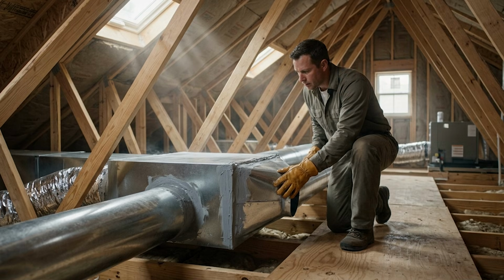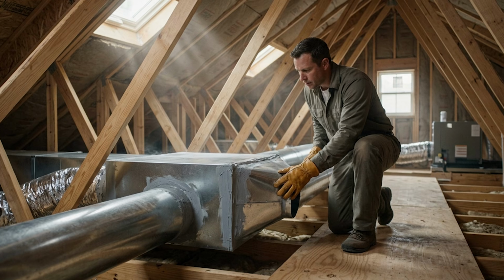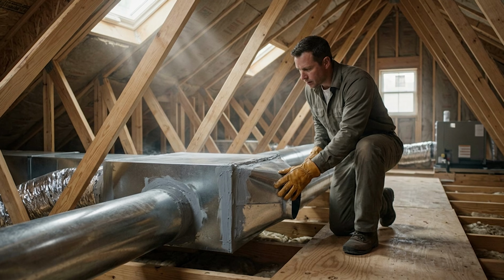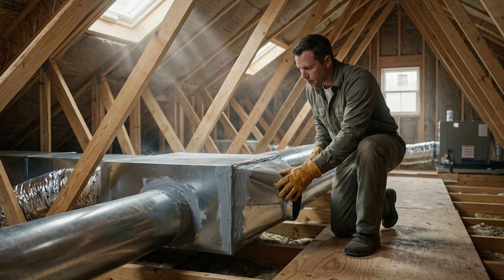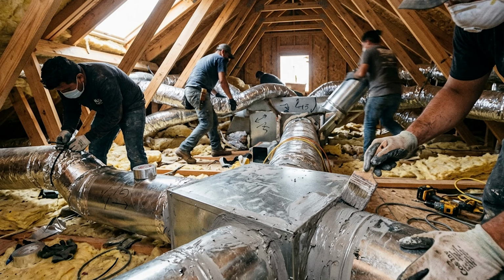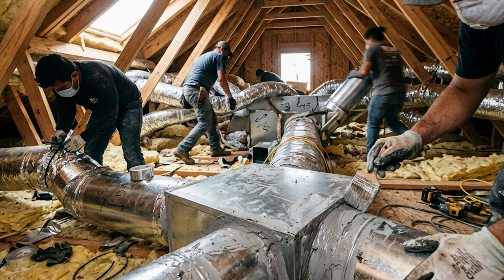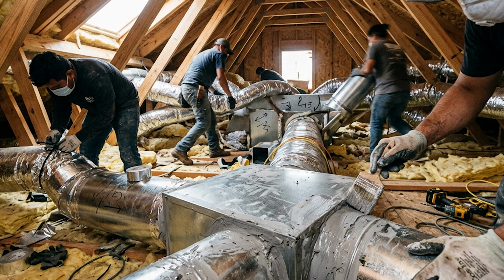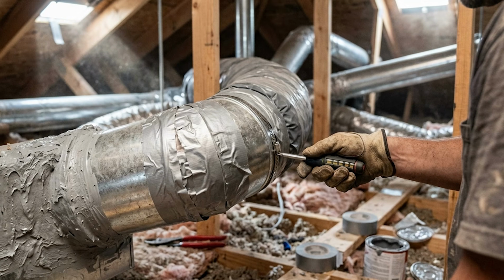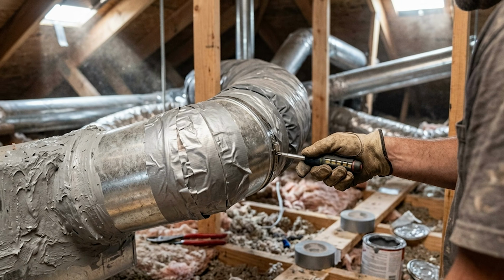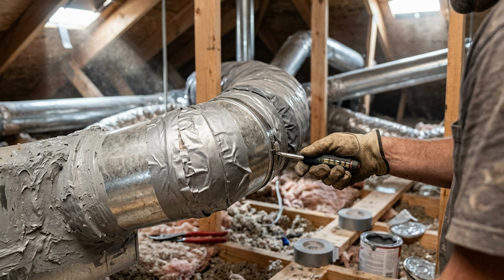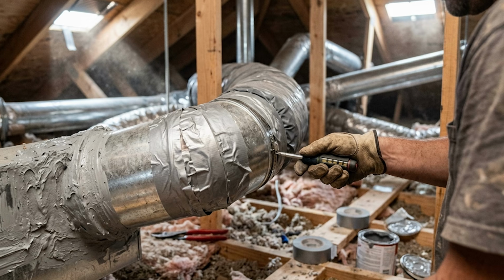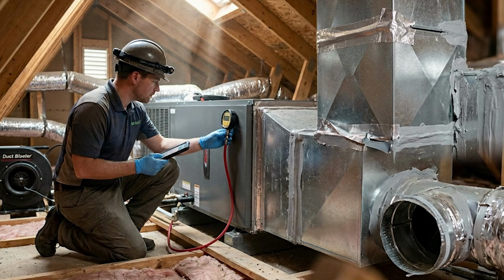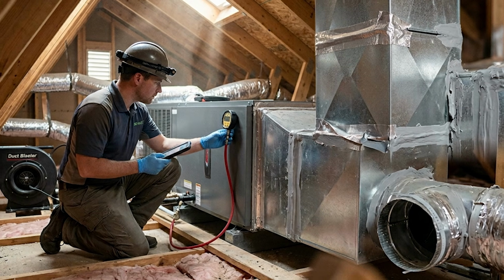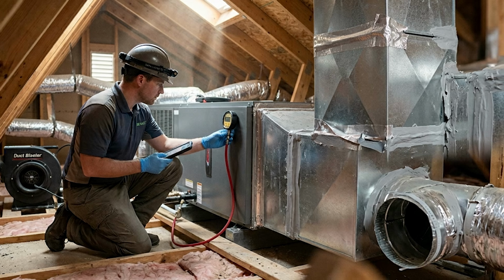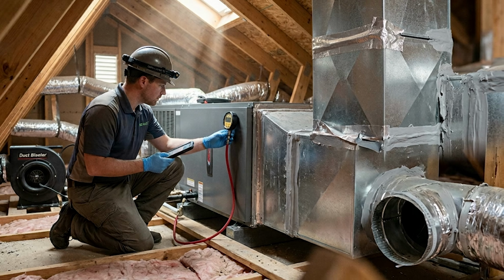Let me also tell you something about new homes, because a lot of people assume this is only a problem in older houses, and that assumption is wrong. New construction HVAC installs are done under time pressure. Crews are moving fast. Duct connections are often assembled quickly and secured with a single wrap of duct tape, which, as we discussed, will fail within a few years of installation. Energy auditors who test new homes regularly find that brand new houses fail duct leakage standards by significant margins.